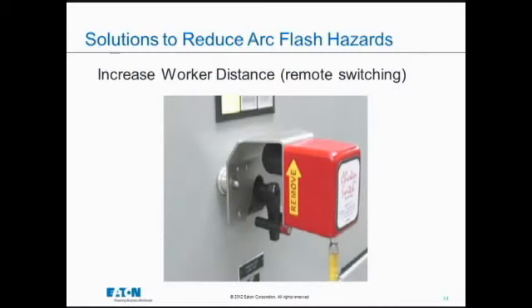So I'm just going to go through a few of the solutions. One of them is move further away, and this is the chicken switch. Now, the chicken switch is not an Eaton product, but you could put a chicken switch on an Eaton product. It's generally intended to move about from one place to the other. It's magnetically held, and it just takes the place of a person's hand operating a switch handle. Rather than moving it from side to side with your hand, you put the chicken switch over the handle, and 20 feet back you do the same operation from a solenoid-operated, battery-powered device. So that's a very unique way of remotely switching, moving further back.